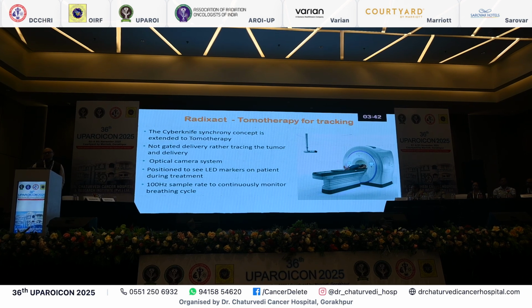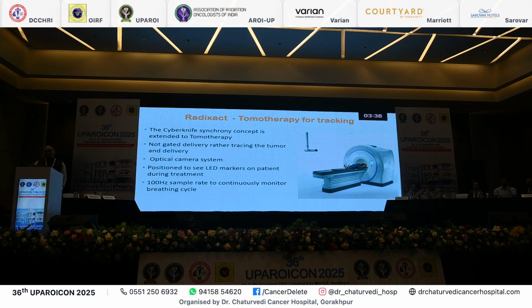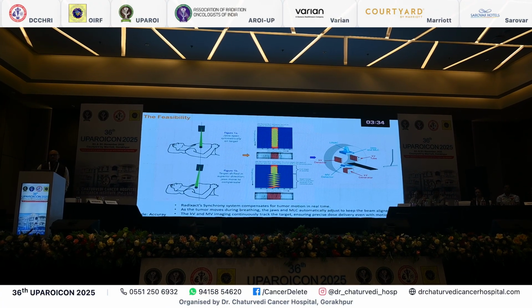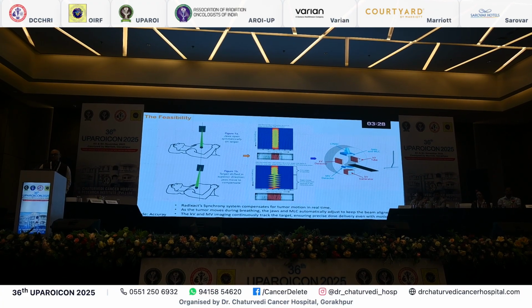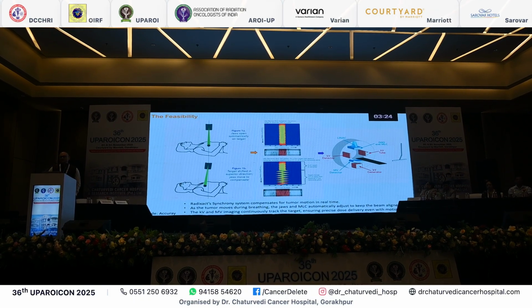The same concept in a slightly different manner is being utilized in the tomotherapy unit also, whereby the kV detectors and MV detectors continuously monitor the target, and as the tumor moves during breathing, the jaws and MLC automatically adjust to the beam, and the beam is kept aligned.